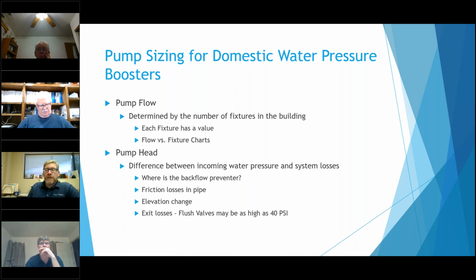There's some of these I've seen where they put the backflow before the pump, and it chewed up all the pressure coming into the pump. So there was only like 5 or 10 pounds of pressure to the pump. So you do have to be careful where that is for proper pump operation. But you're going to need to add up any pressure drop that you see with the backflow, your elevation change, and then your exit losses. Like I said, some of those flush valves can get up to 40 pounds. So you need to be careful with it.